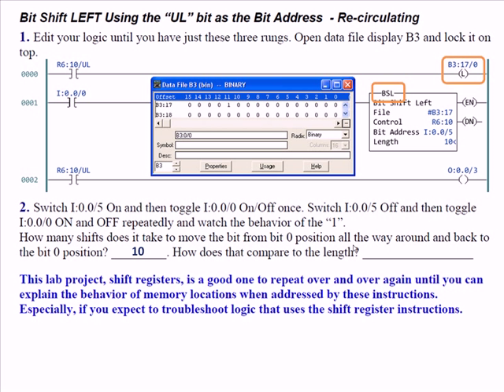The 10 shifts equal the length — the bits recirculate until overwritten with a 0. A practical application is a rotary index table with 10 positions: when a product is loaded into a position, you put a 1 in that station (stations 0 through 9). As it continuously rotates, occasionally a product is taken off and a 0 is written to that position, but the table recirculates continually — so you're not shifting products off the rotary index table, they just keep going around.